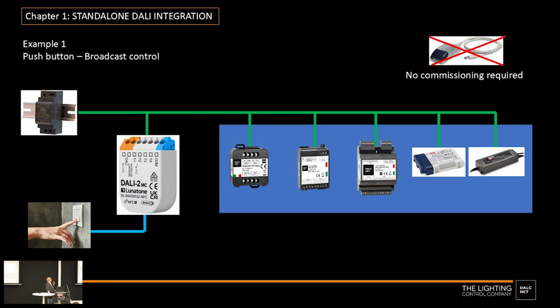This is probably the most simple application, because the push button interface uses a broadcast signal. This means I don't need to do any commissioning or address every device, since the broadcast signal makes every device connected on the DALI line respond to the command — so there's no need to distinguish every single control gear, because they all behave the same.